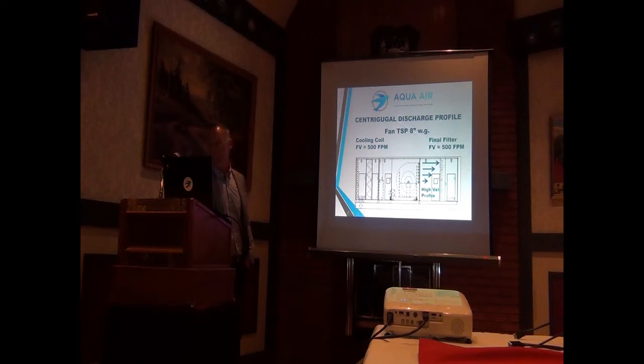This is a front loading face one, it looks like, but still, you're talking about really high velocities. You can correct that through air blenders and other things, but then your unit just gets larger and larger and larger. Typically with this, when you have a discharge like this, you'll have one opening in the bottom, opening in the roof, say, or opening in the end.